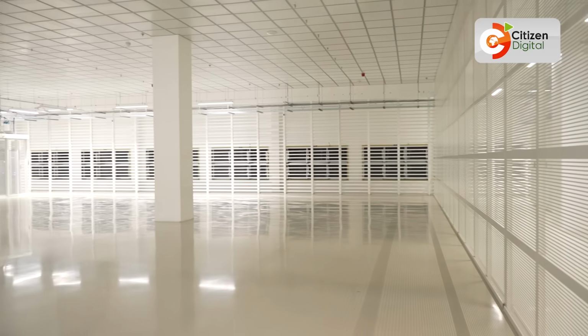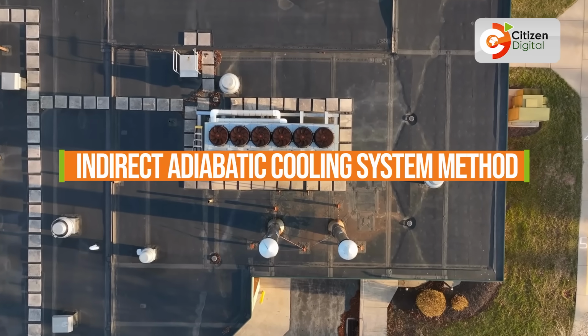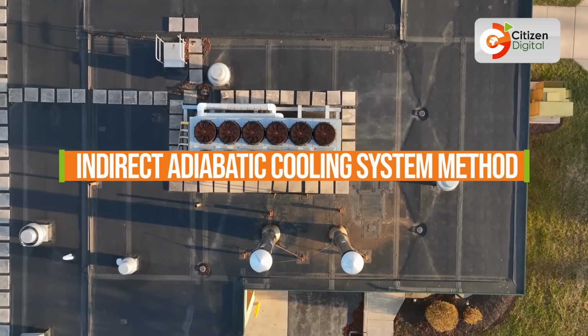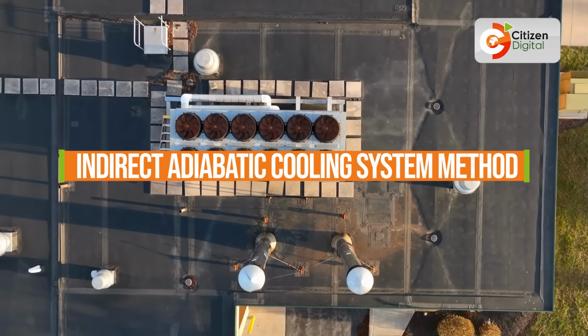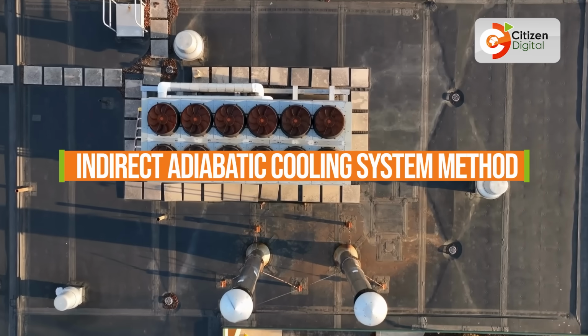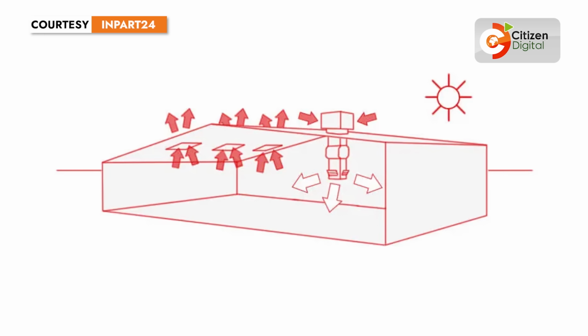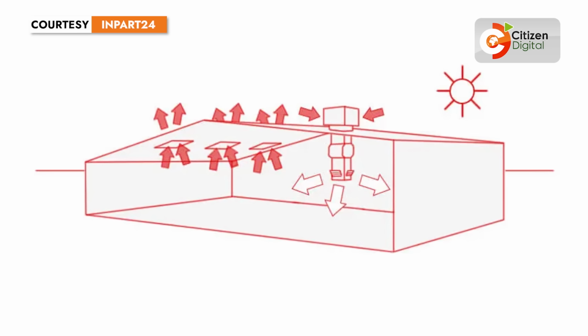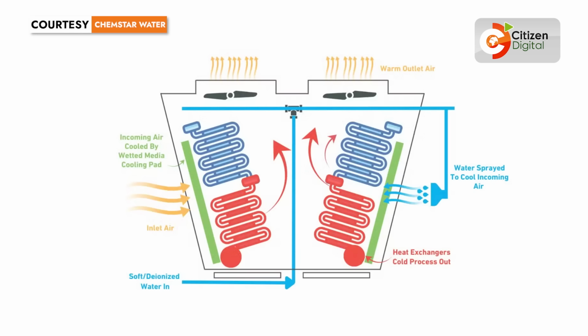The mega facility is cooled by an indirect adiabatic cooling system method, which uses evaporative cooling to cool air without adding moisture to it, by passing air through a heat exchanger. The heat exchanger has two separate air streams: one stream of warm outside air that is cooled by evaporation, and another stream of inside air that is cooled indirectly by the first stream. This system allows for efficient cooling and energy saving.